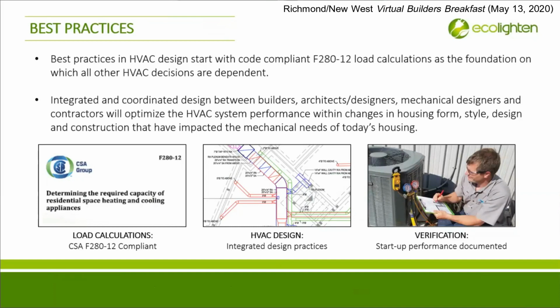Get them to coordinate with the design team. For example, a homeowner, architect or home designer, a builder, structural engineer. Included in this process would be clarifying client expectations, providing system options, addressing duct routing issues and installation obstacles. Get them to provide a design that everyone is happy with. Get them to install as designed. And if the designer and the installing contractor are not the same, get the designer to inspect the installation to ensure it meets the design intent at an acceptable standard of practice. And finally, get them to commission the system properly and thoroughly before occupancy.